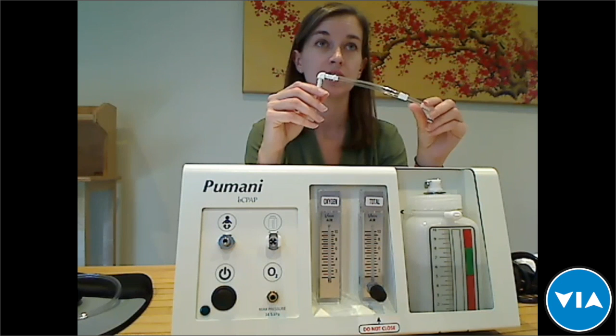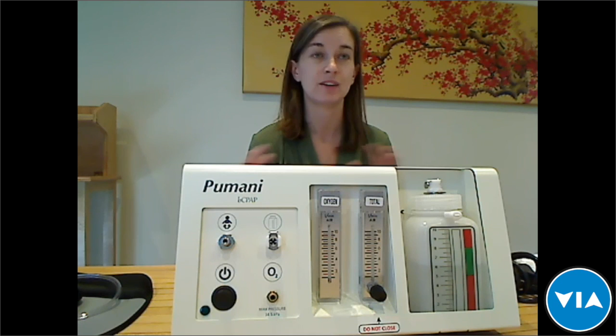Perfect. The next question is related to continuous use: how long can it be used continuously? Yes, we have had several machines used in our office for over 3 years continuously. We've never turned them off, and they're still functioning perfectly. In a clinical setting that's not usually the case. Babies are typically on CPAP for 5 to 7 days on average. Some babies can be on for 3 or 4 weeks if they have a really severe condition. But even then, once the baby is off the therapy, the clinician may turn off the machine for a few minutes or a few hours, and then it can be turned back on and used for weeks or months at a time. So there's no need to turn off the machine and let it rest. It will function perfectly fine for weeks or months or even years, so that's not a concern.